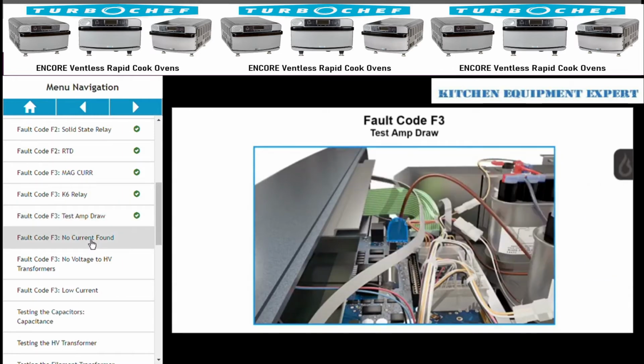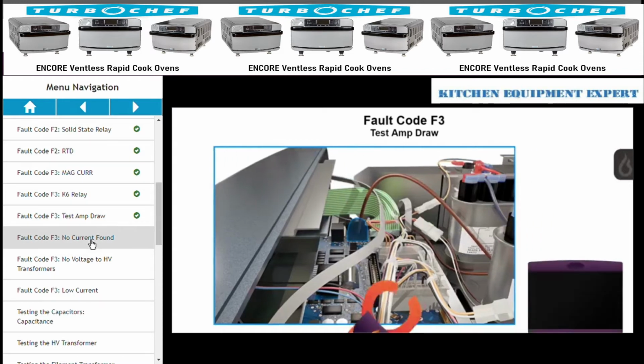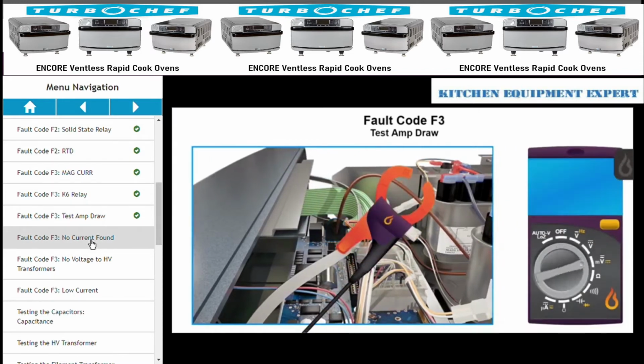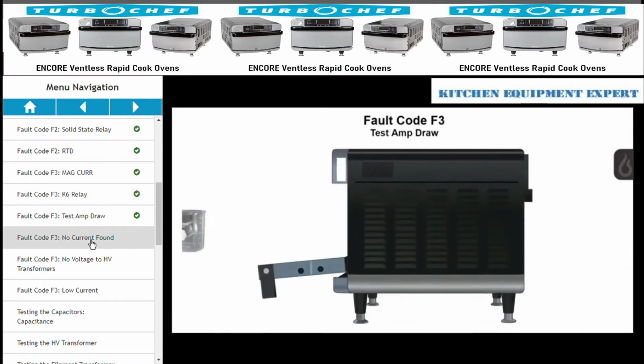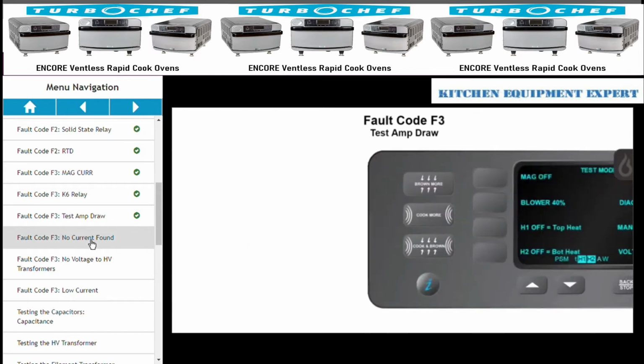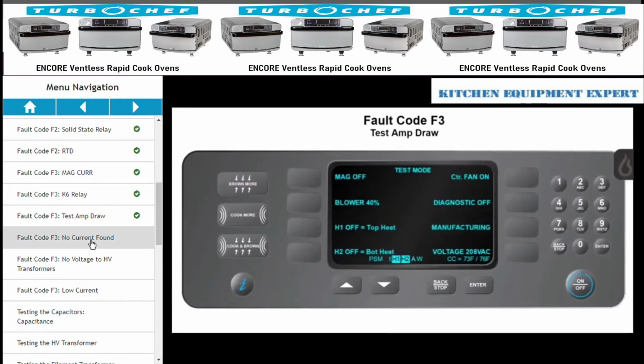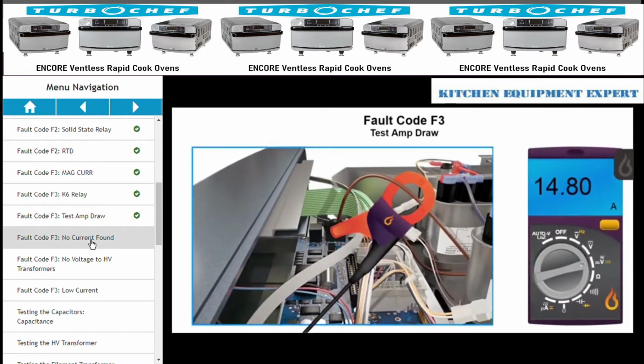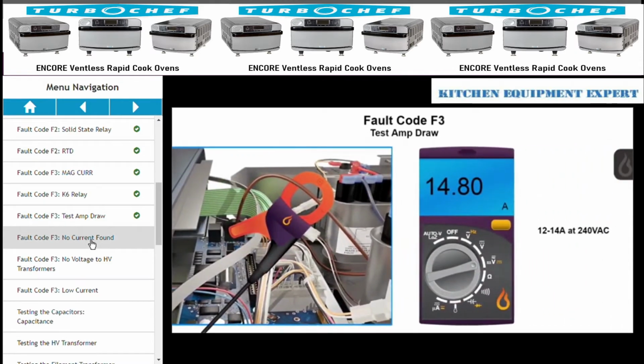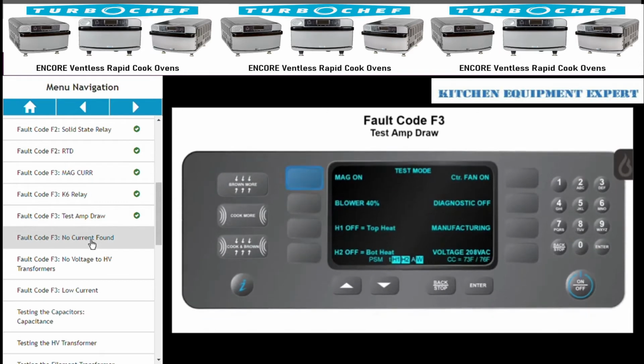It runs through the induction loop on the main control board. With your amp clamp set to AC amps, place the jaws around the brown wire. You'll be turning on the microwave circuits, so put a load in the oven cavity. From the test mode, press and hold the soft key next to mag off. Look at your amp reading. You should see 12 to 14 amps at 240 volts, and 14 to 16 amps at 208 volts. Release the soft key to turn off the microwave circuits.